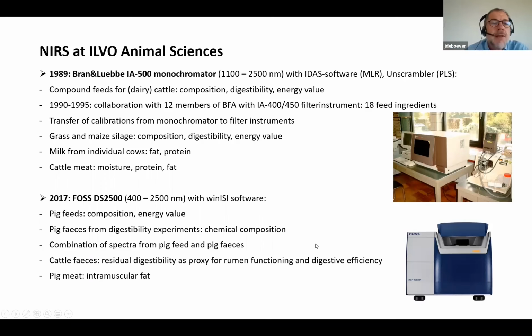We started at ILVO Animal Sciences in '89 with a scanning monochromator in the wavelength spectrum from 1100 to 2500 nanometer, in first instance to develop calibrations for compound feeds for ruminants. We worked together with members of the Belgian Feed Association, which at that time disposed of filter instruments. And we developed calibrations for 18 feed ingredients, of which calibrations were transferred from our instrument to their instruments.